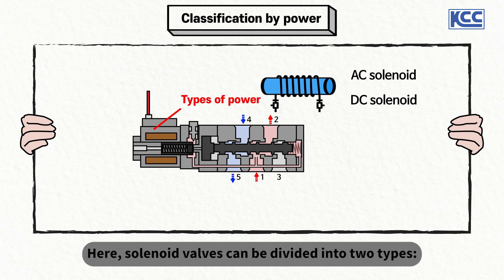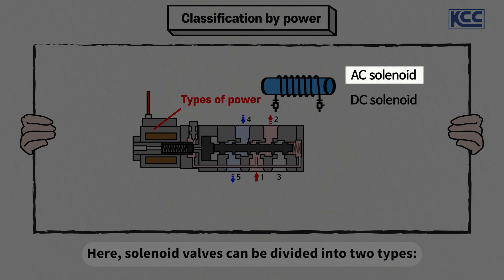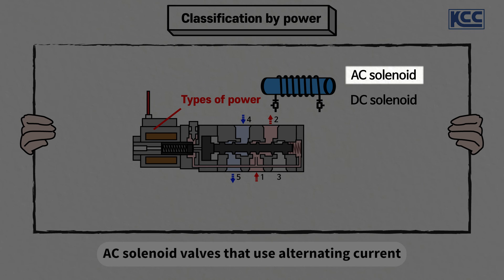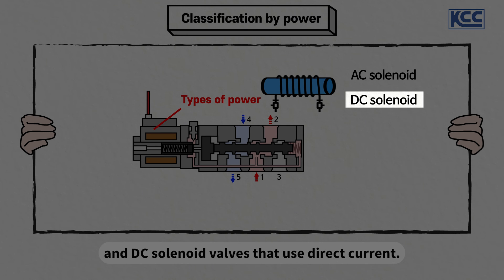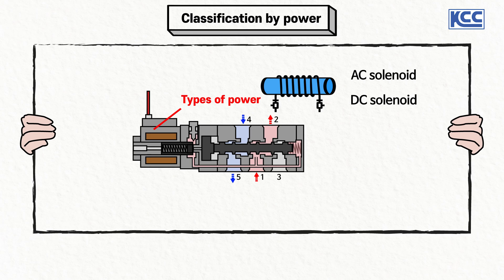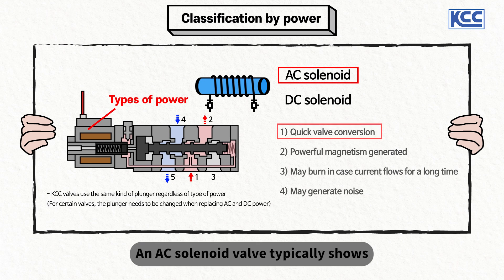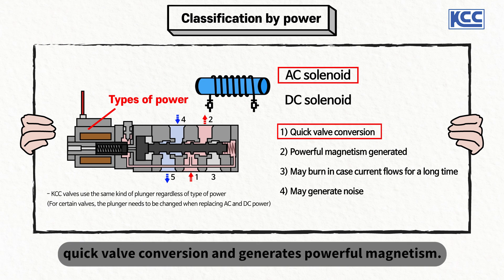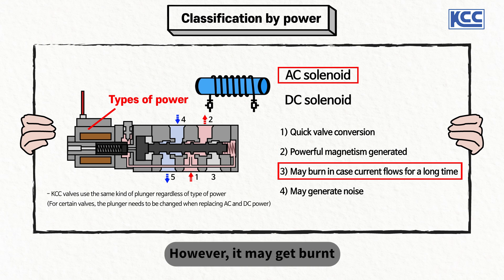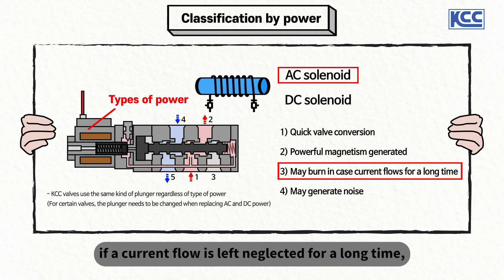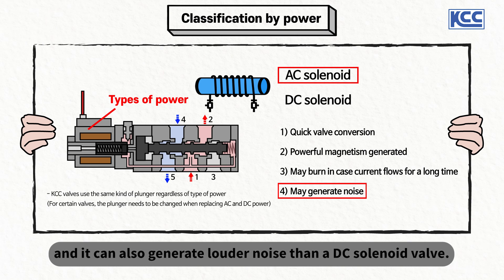Solenoid valves can be divided into two types: AC solenoid valves that use alternating current and DC solenoid valves that use direct current. An AC solenoid valve typically shows quick valve conversions and generates powerful magnetism. However, it may get burnt if current flows for a long time, and it can also generate louder noise than a DC solenoid valve.